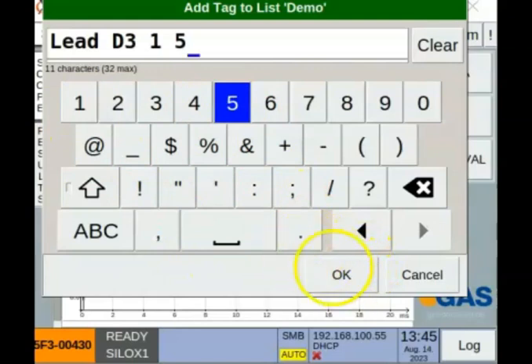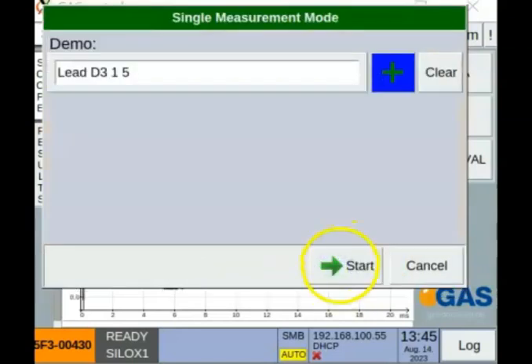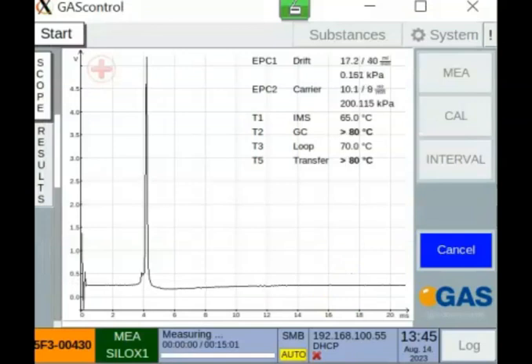Reaction of D3, and we start the measurement. The measurement progress is shown here. In the first 30 seconds, the system goes to the default flow of 75 milliliters during the measurement, and the EPC carrier gas is set to 5 milliliters.